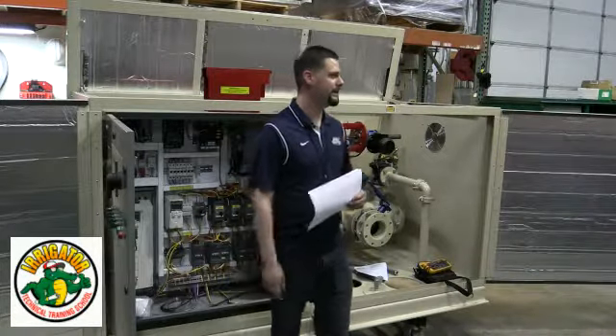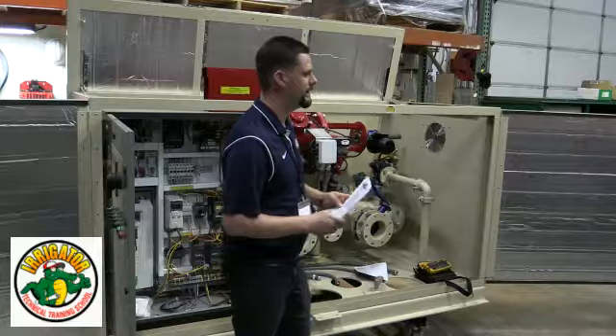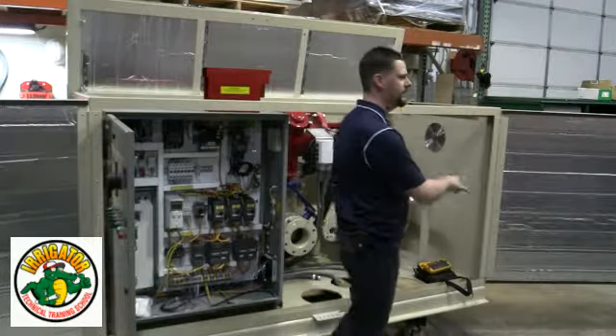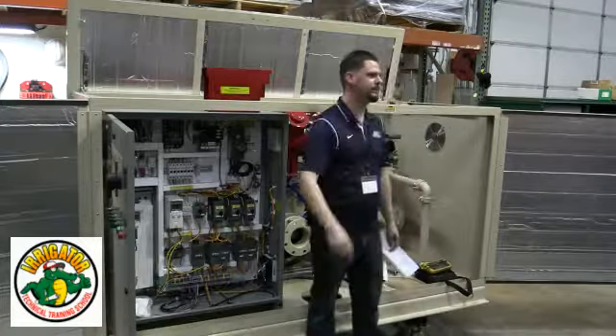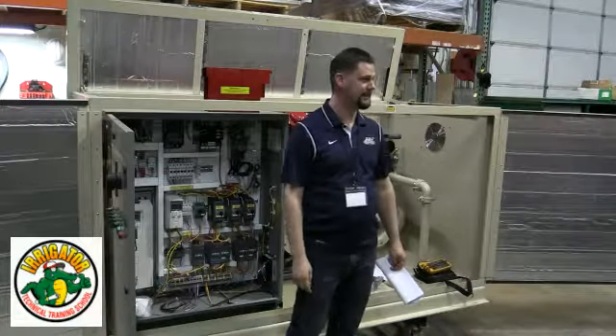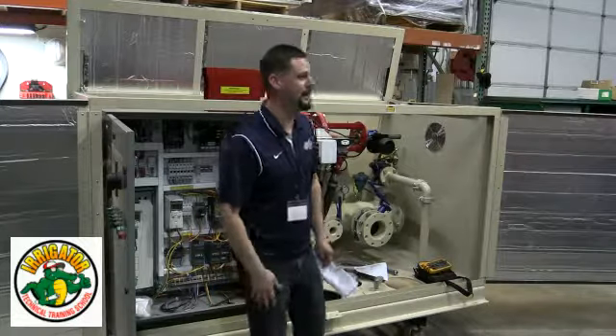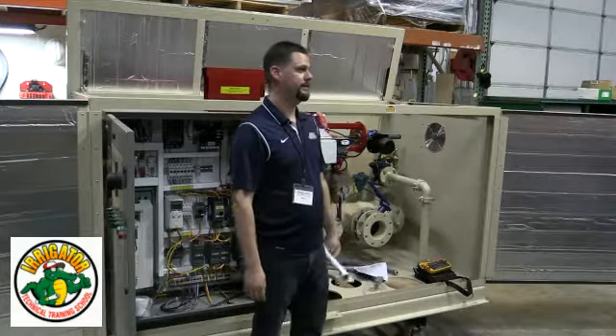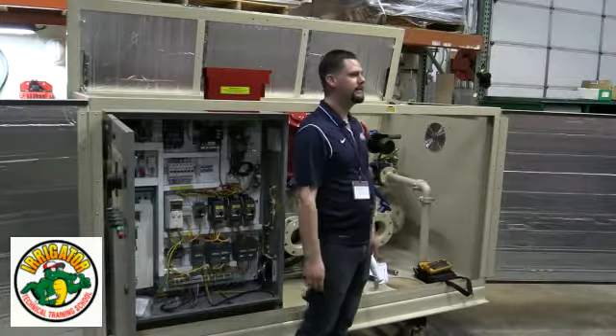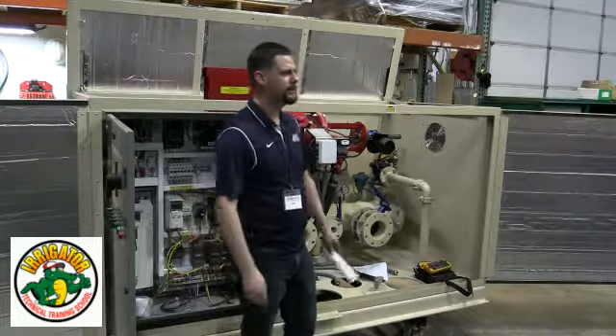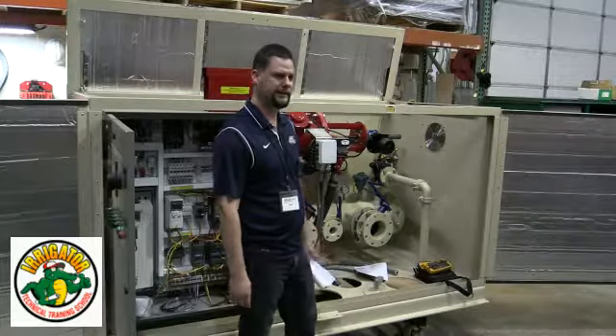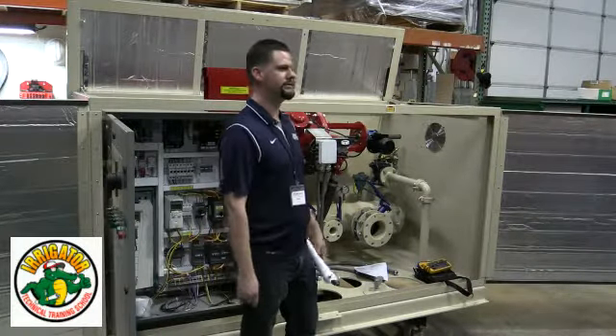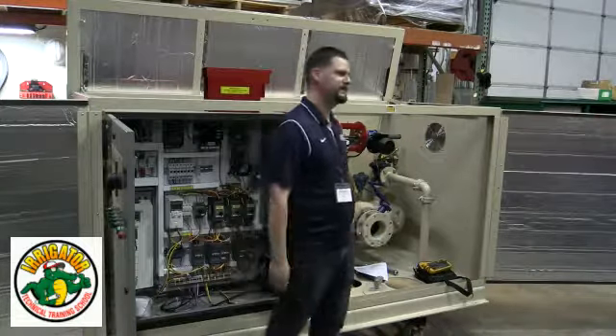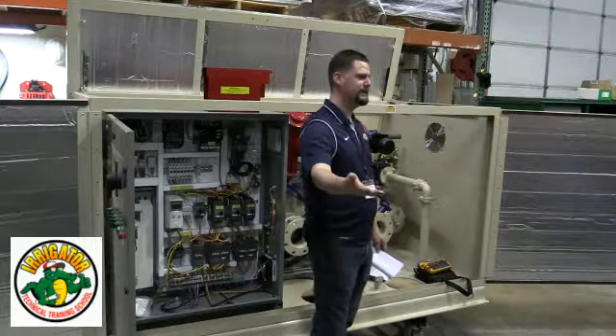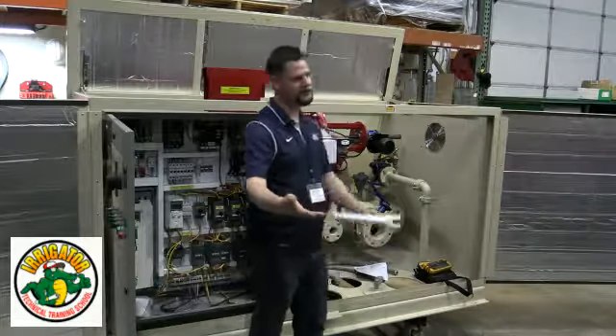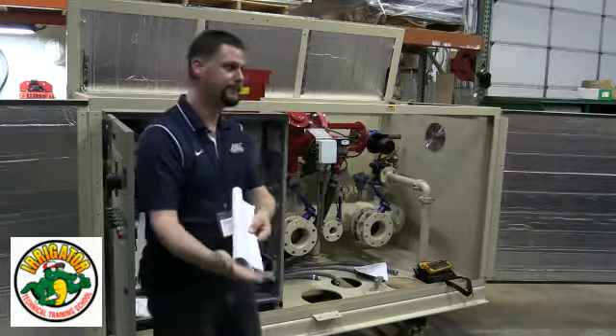A couple of years ago we had a pump station, they had a main break. This was a huge pump station. It was a 4-inch main break down their main line a ways, and it didn't shut down because it could still maintain 50 pounds for an entire weekend. It caused a lot of damage, and there was a lot of complaints coming up. People were pissed, and they tried coming back at us saying, hey, your pump station didn't shut down when it was supposed to. Well, let's talk about this. It was maintaining pressure this whole time. So how are we supposed to know, based on it only doing 50 pounds, that there's a main break?